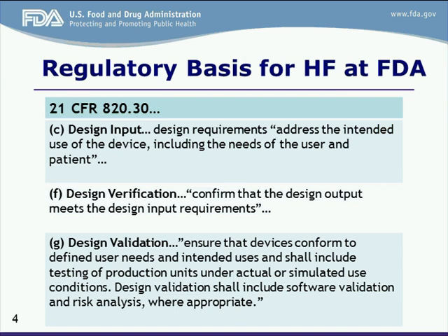And then design verification and design validation. One thing I would want to note here is design validation, to read the quote, is to ensure that the device conforms with the defined user needs and intended uses. One thing I want to make sure we point out here is we'll be talking about human factors validation. Human factors validation is looking to show that the user interface supports safe and effective use. When you're looking at those definitions side by side, that is a subset of design validation. They're not synonymous per se. But human factors validation may answer some of your design validation needs. Make sure we're clear on that.